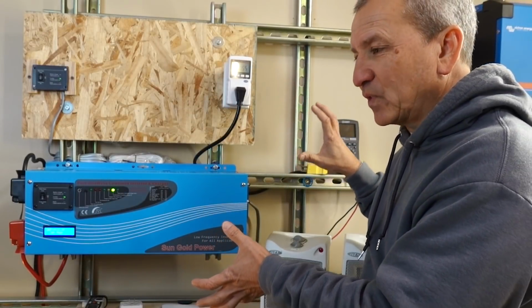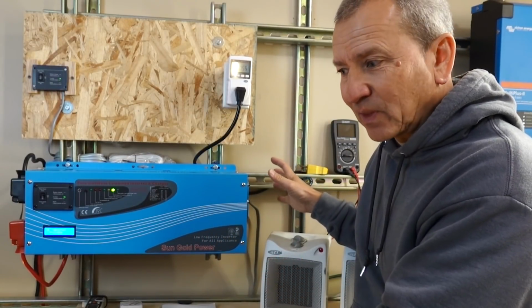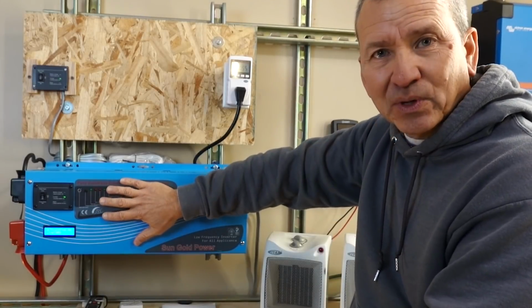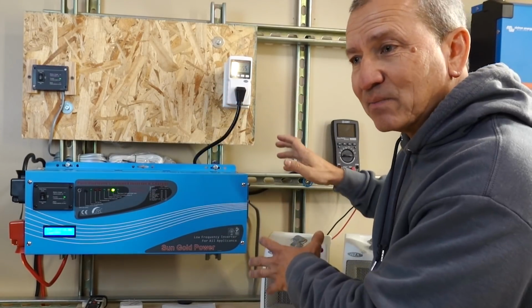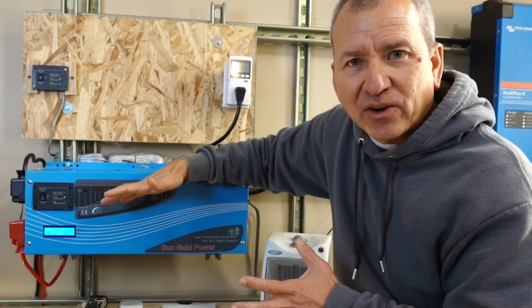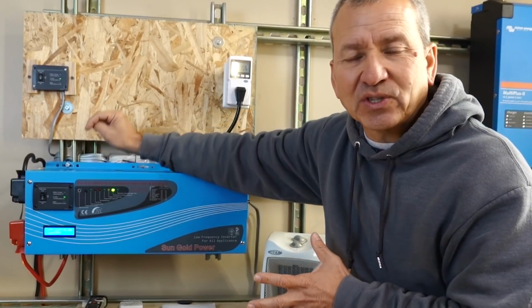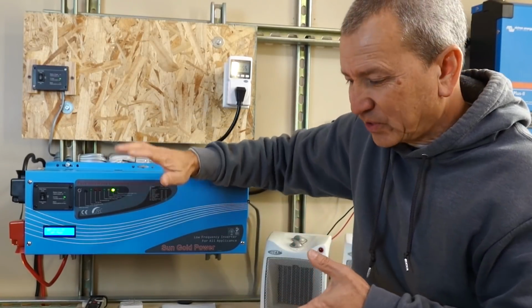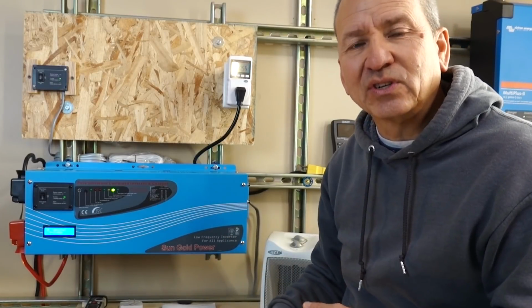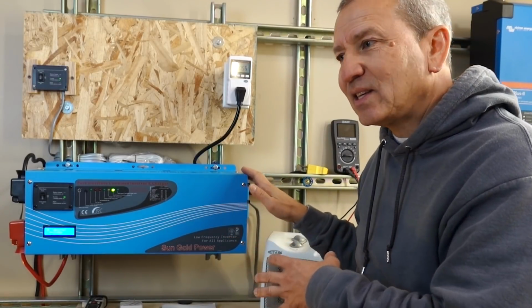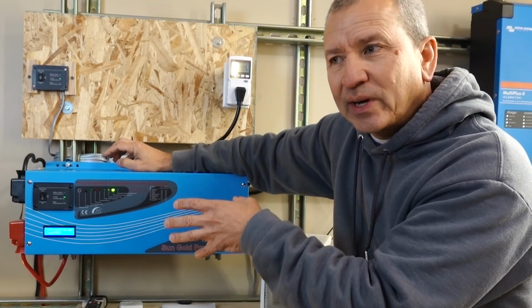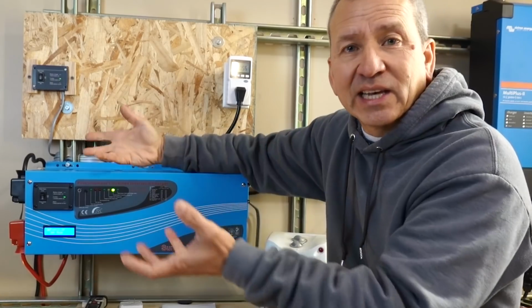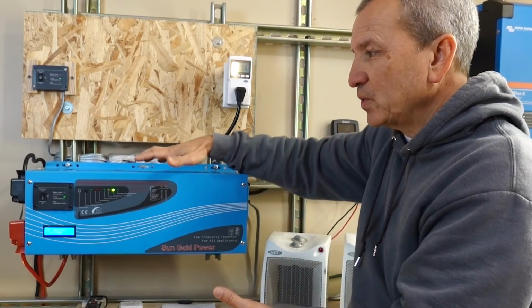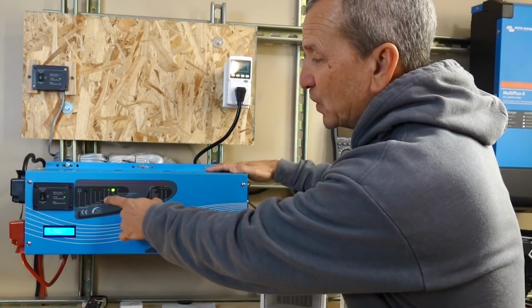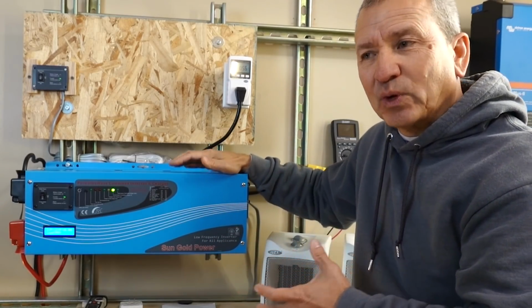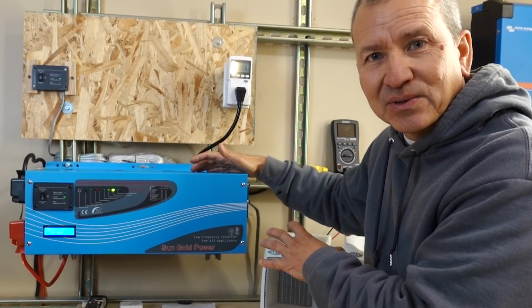If you were connected to the grid or AC power in that battery priority mode, then it would run off of battery power in inverter mode, and then it'll only switch over to the AC mode if you reach that low battery cutoff point. There's two settings in the dip switch that you can set it to, 10.5 or 10 volts. So when your battery gets down to that low voltage level, only at that point it'll switch to AC. And what you could do though is that if you had a generator auto start set up also, then it'll automatically kick on your generator, and then it'll switch to AC mode and charge mode, recharge your batteries, and then once your batteries are fully charged, then it'll switch back to battery mode.